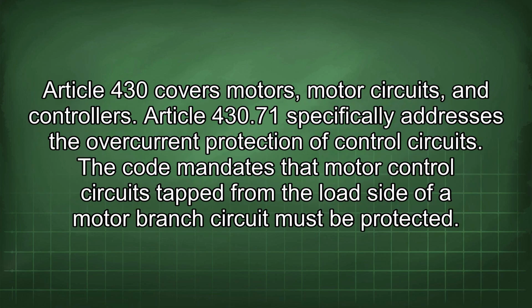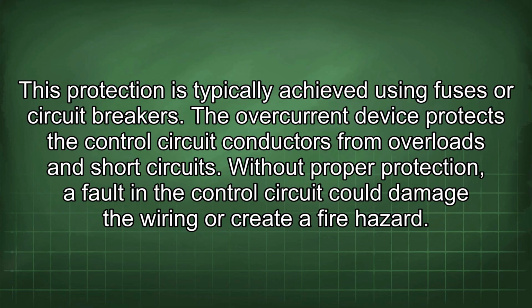Article 430 covers motors, motor circuits, and controllers. Article 430.71 specifically addresses the overcurrent protection of control circuits. The code mandates that motor control circuits tapped from the load side of a motor branch circuit must be protected. This protection is typically achieved using fuses or circuit breakers. The overcurrent device protects the control circuit conductors from overloads and short circuits. Without proper protection, a fault in the control circuit could damage the wiring or create a fire hazard.